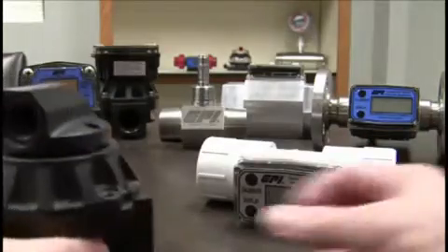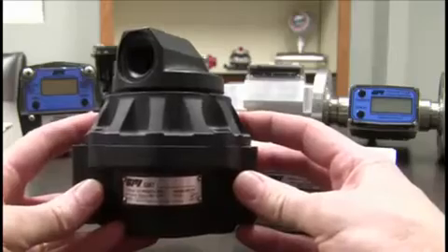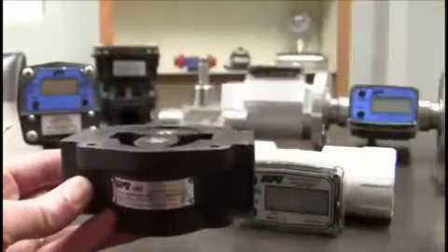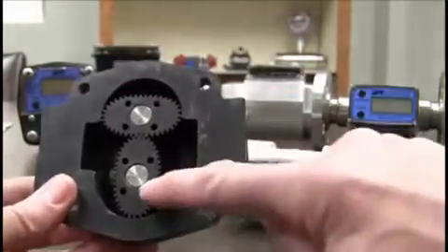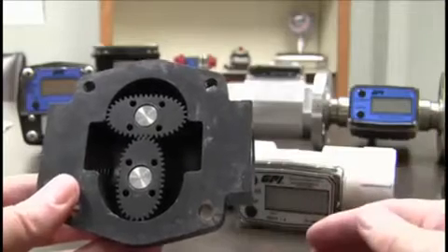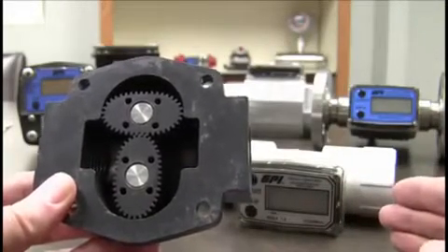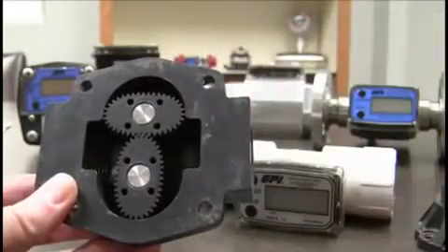Here's a nice positive displacement meter. It's a 1-inch. And this one's just going to be a pulse out as it is. Now the nice thing about a positive displacement meter is exactly what it says. It's positive displacement. If you look inside, you've got two oval gears. That's why we call them oval gear positive displacement meters. Sometimes you call them just one or the other term, but either way it means the same thing. And you see this little chamber here. That is where the fluid goes through.